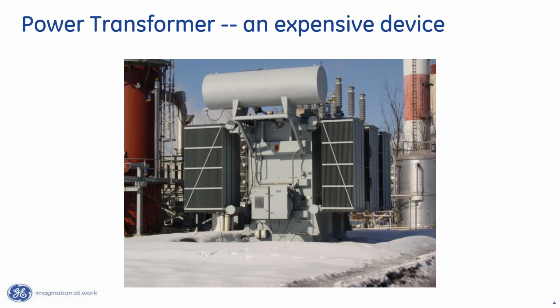So transformers, by and large, are important because they are a large, expensive device. Now, the transformer that you see here has a conservator tank. That looks like a transformer that's around 50, 60 MVA. If we're going to buy a transformer of that size from a normal manufacturer, we've probably got a lead time of around a year. When I last bought transformers, which is 12 years ago or so now, we had a lead time somewhere between 9 months and a year.